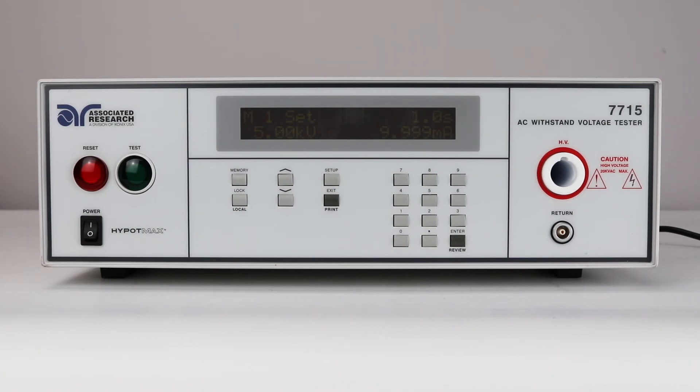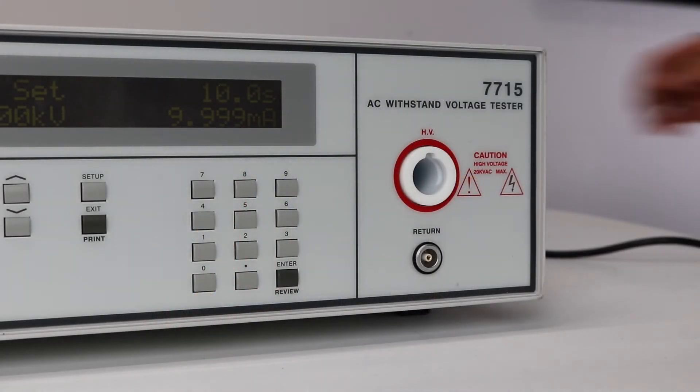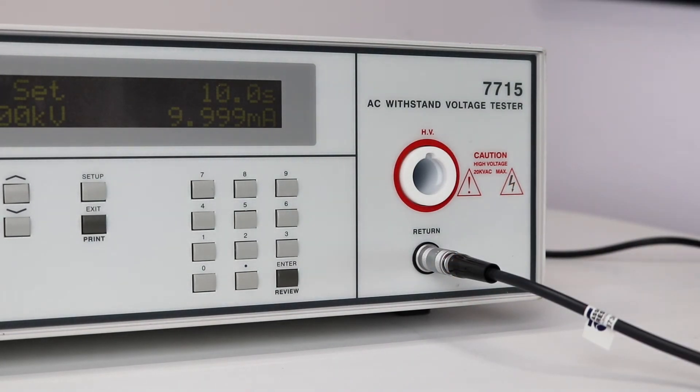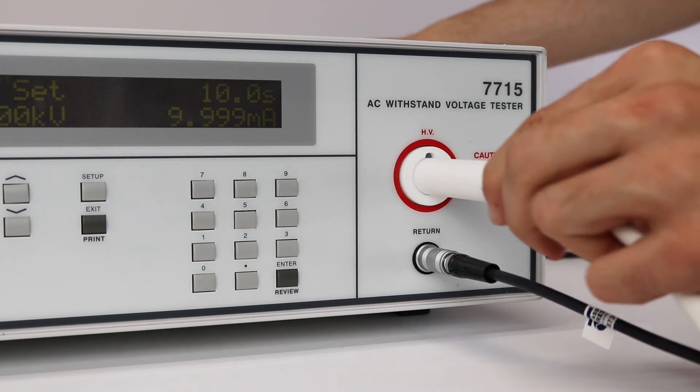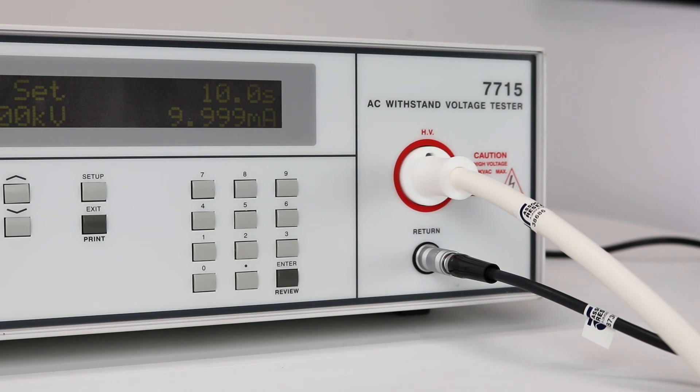Finally, we're going to show you how to connect the HypotMAX to a DUT and run the test sequence. To connect the HypotMAX to the DUT, you're going to need the following accessories: the red high voltage lead and the black clip return lead. First, connect the black lead to the return terminal on the HypotMAX. Connect the high voltage lead by plugging in the white Alden-style connector to the HV terminal. Be sure to line up the plastic knob on the HV lead with the slot on the HV terminal on the HypotMAX. Once inserted, turn clockwise and lock the lead into place. Once all these connections have been made, you can now connect your DUT.